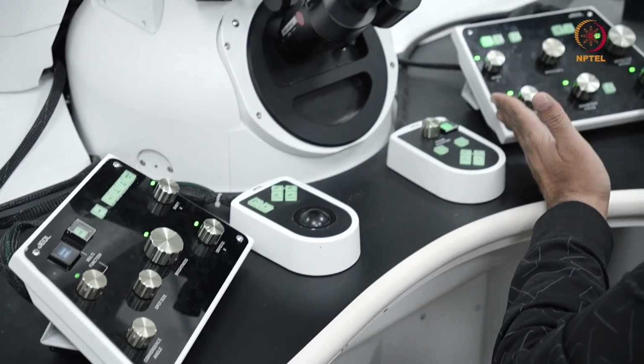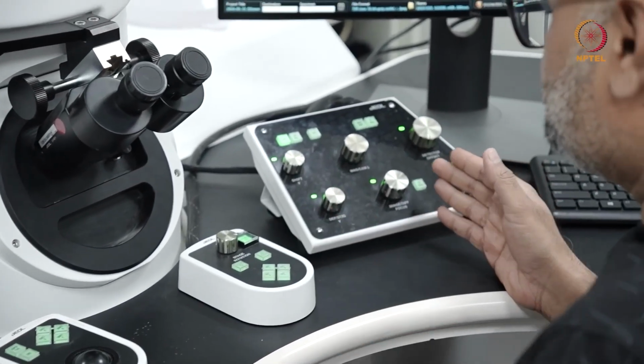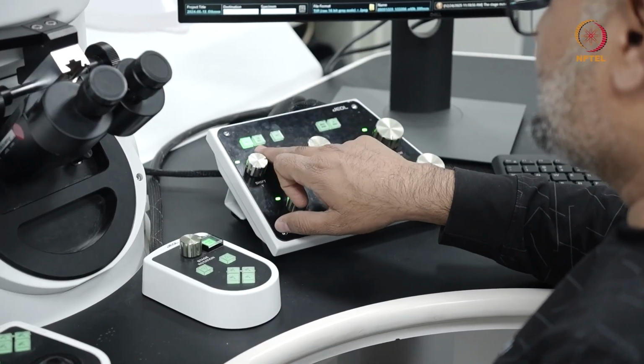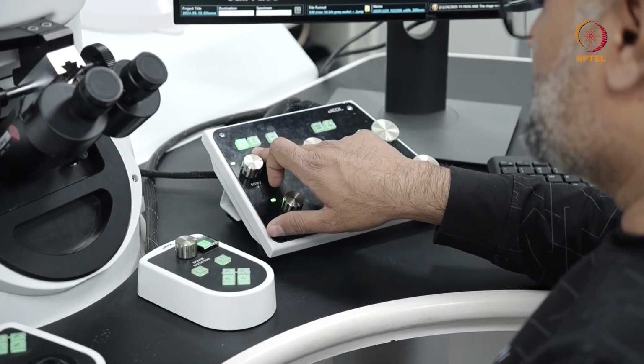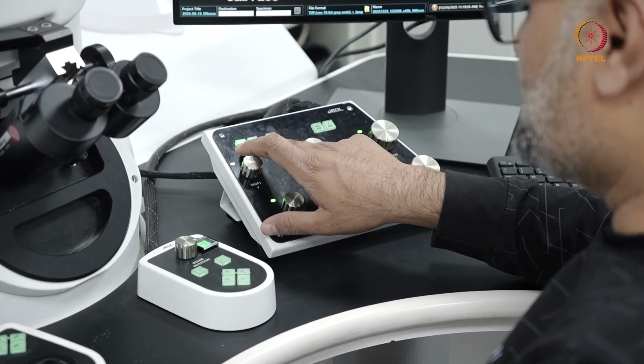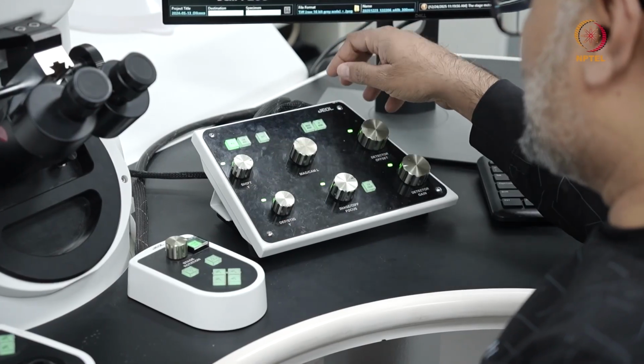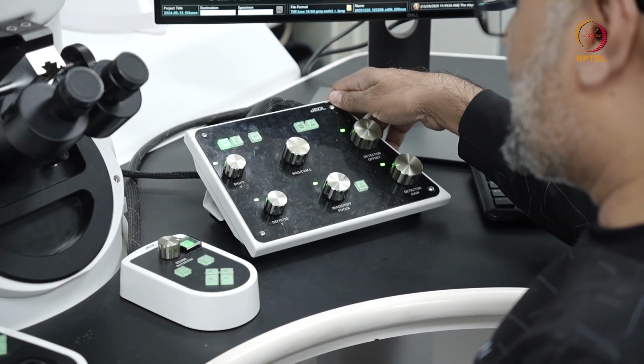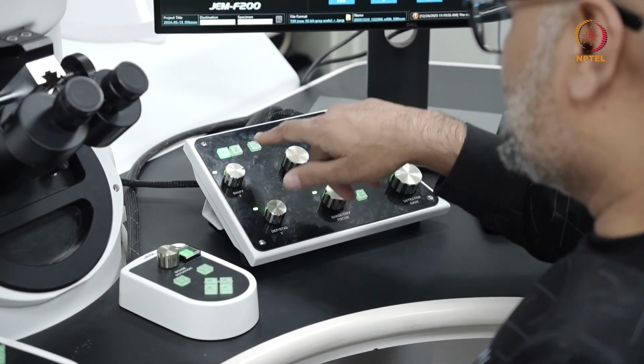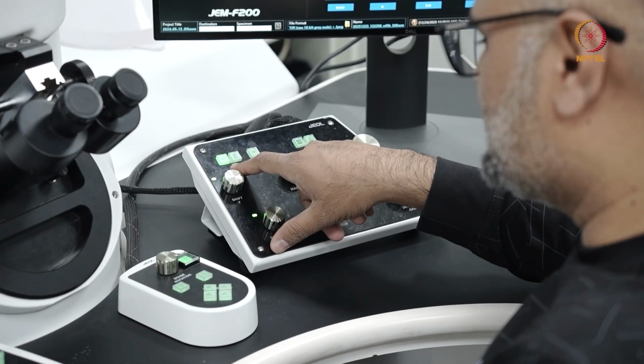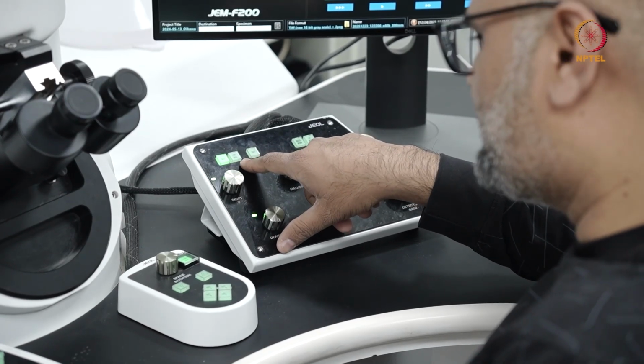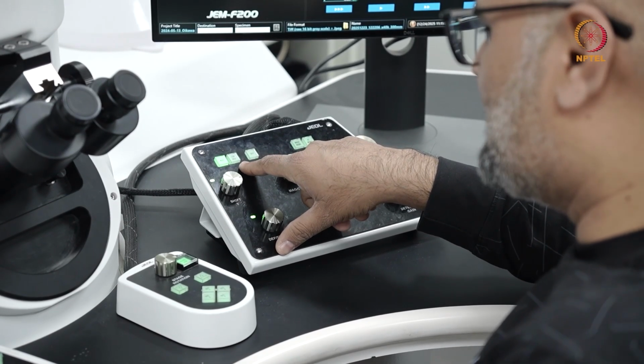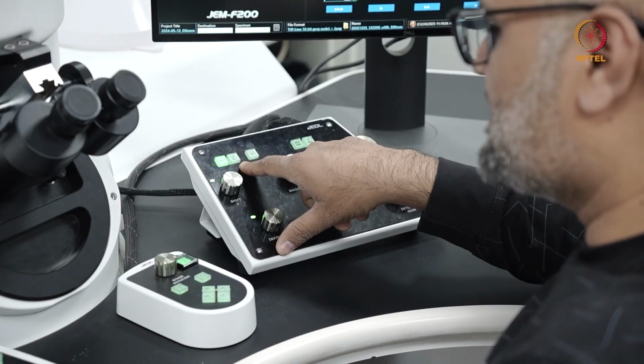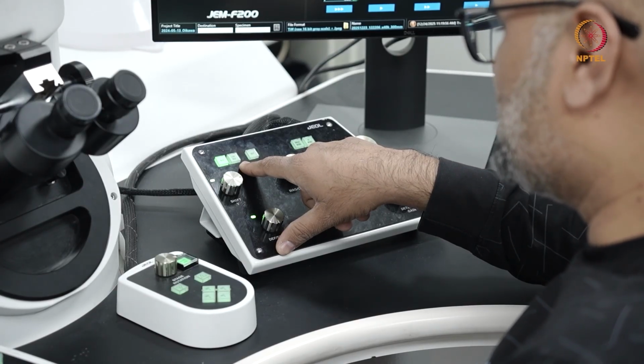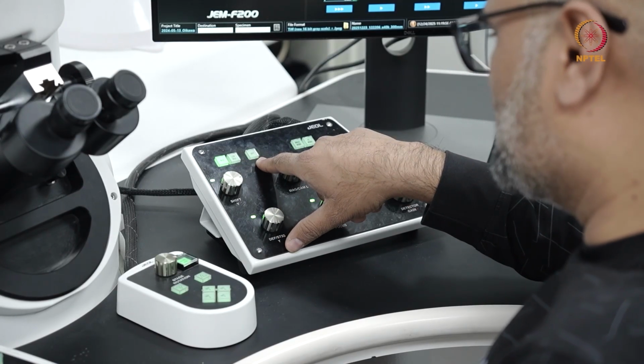If I focus onto the right side panel now, what you have here is to choose the different modes of magnification. Unlike in the other instrument where you had mag 1, mag 2 and SA mag, you only have one mag mode here, and then you have the low mag mode. When you switch into the low mag mode, you are also switching into the Lorentz mode on this particular instrument, and then you have the diffraction mode.